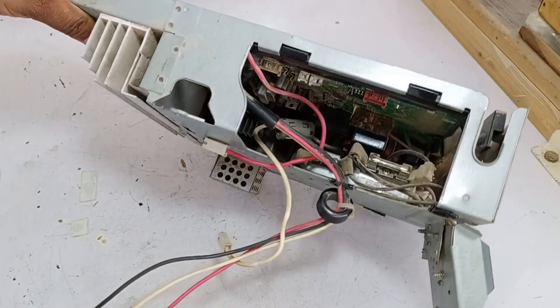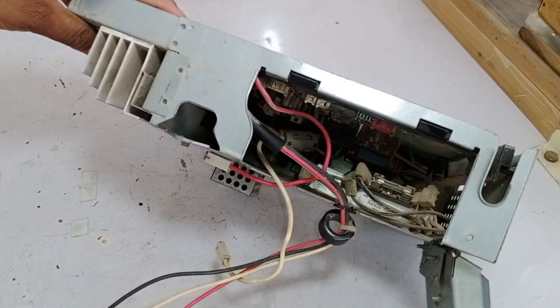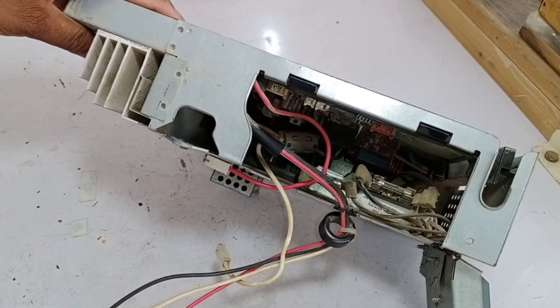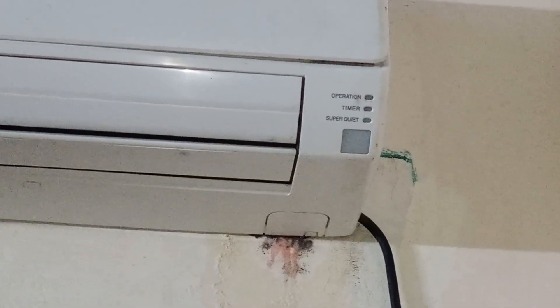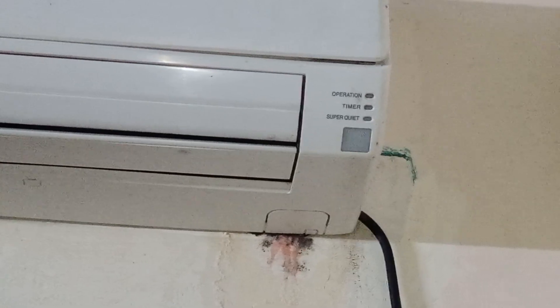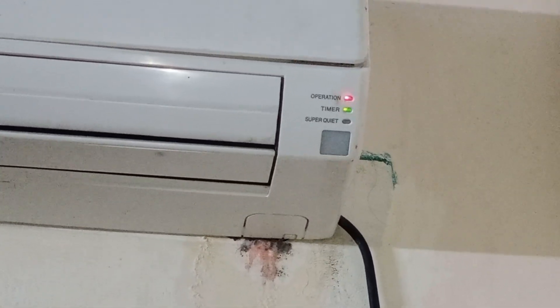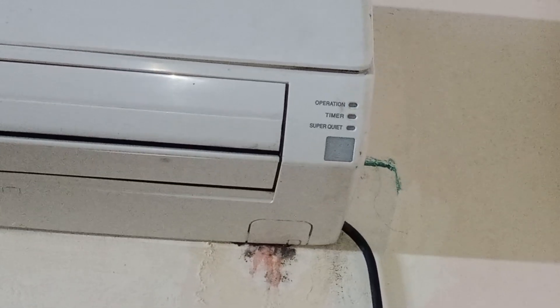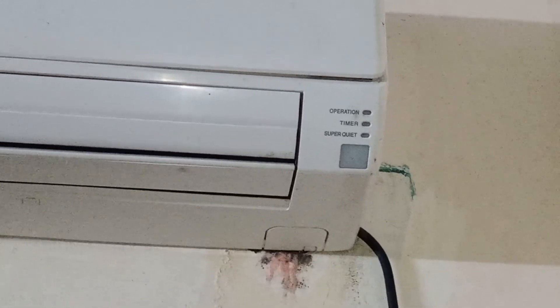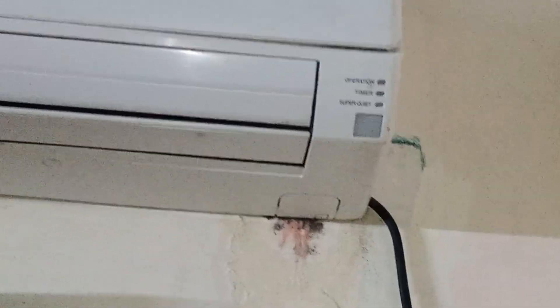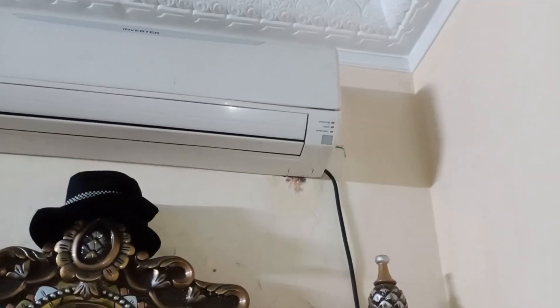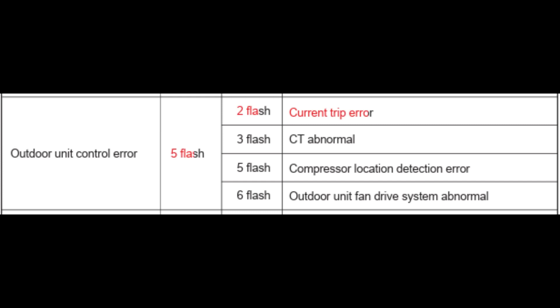The customer has sent me a video of the fault this mini split air conditioner was showing on the display. This is the video the customer sent me, so let's count the blinks: 1, 2, 3, 4, and 5. The timer light is blinking 2 times, and the operation light is blinking 5 times. This is a current trip error in this Fujitsu mini split air conditioner.